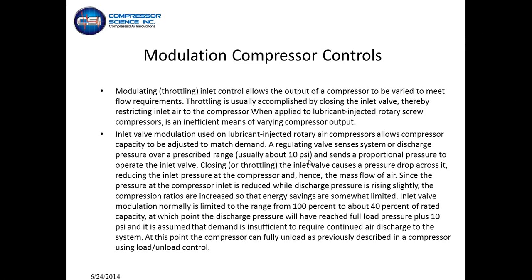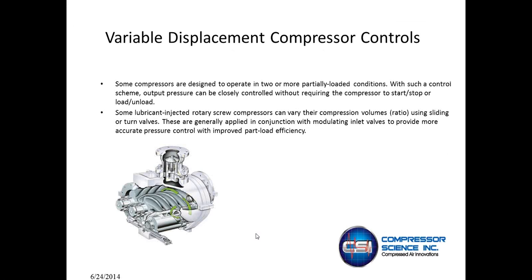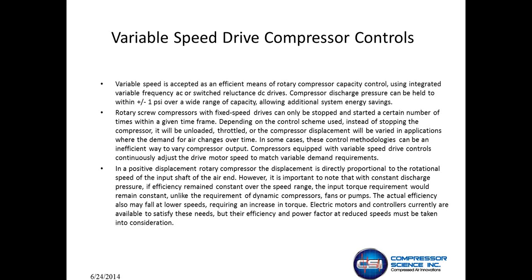Okay, variable displacement basically changes the rotor length on the compressor, so it drops the amps on the motor. You're changing the compressor volume or ratio using a sliding vane or a turn valve. Those are usually applied in conjunction with modulating valves to provide more accurate pressure control, but you're getting part load efficiency. Last are variable speed drive compressors, where the compressor changes its energy consumption by modulating the motor up and down to maintain a steady pressure. These will maintain a steady pressure within a certain range, and the motor will ramp up and down in order to consume less energy.